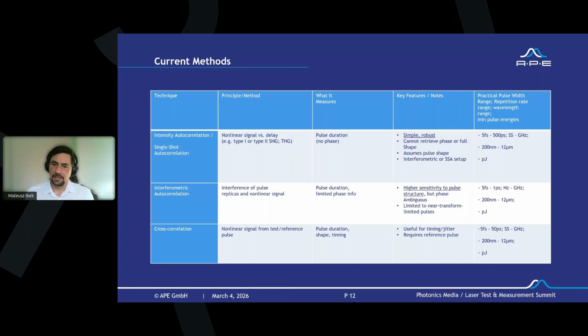The range in which this works, the laser specification range, is quite wide. It's around 5 femtoseconds to 500 picoseconds or more. It is single shot capable. It goes to gigahertz repetition rates. For wavelength ranges, the longest that we can measure with autocorrelators is 200 nanometers to 12 micron, and sensitivity is in the picojoule range.